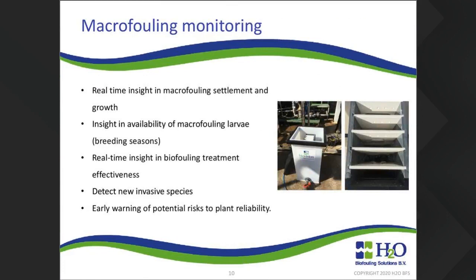Now, for macrofouling monitoring, you can use a monitor which is shown in these pictures. And this monitor we developed provides real-time insight in macrofouling settlement and growth rates of all different kinds of macrofouling species. It also provides insight in the breeding periods. So macrofouling is not available throughout the whole year. Depending on the location and depending on the species, you have specific breeding periods where the animals release larvae, which enter a cooling water system and which can settle in a cooling water system itself. So you can use the monitor to tailor your dosing period throughout the year based on breeding periods and availability of larvae. It also detects new invasive species.